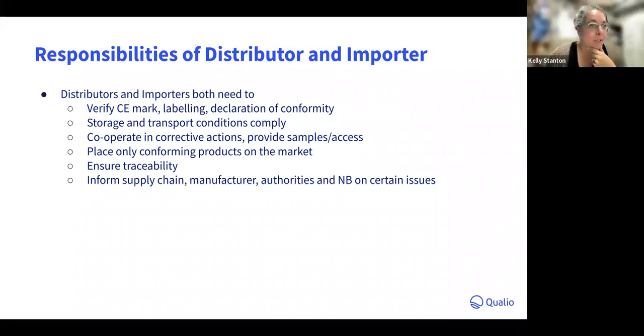I just want to jump in here really quickly and say, these are the kinds of things notified bodies will look for in your quality agreements with these distributors and importers. Those designations and requirements are especially around reporting of issues in a timely manner. Those are the kinds of things the inspectors are going to look for, and they need to be very detailed. You need to have processes built on both sides. So you as the sponsor need to make sure your distributors have appropriate processes and timing in place for when they notify you of a problem. One of the toughest situations you can get into is a back and forth about who knew when that a problem had happened and how that information made it back to the manufacturer. That's easy fodder for inspectors if you don't have that process well defined and spelled out in your quality agreements between yourselves and your distributors.